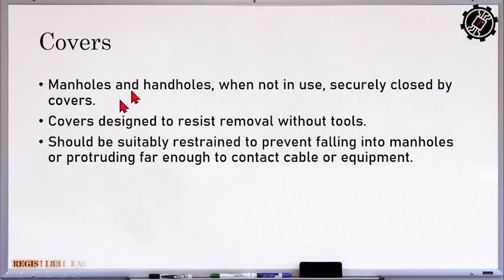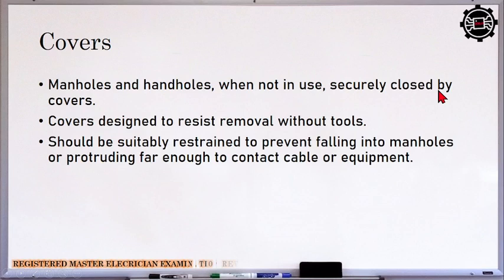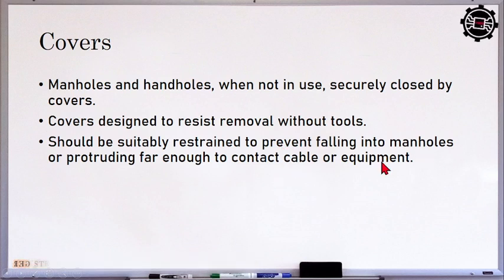So the cover, manholes and handholes when not in use must be securely closed by covers. So covers is designed to resist removal without tools. No, so dapat pwede lang ma-open yung mga cover ng ating manholes and handholes if there is specialized tools to be used, no? So basically, only the qualified person could access our manholes and handholes. Should be suitably restrained to prevent falling in the manholes or protruding far enough to contact cable or equipment. So dapat may siya tamang support so that walang mga taong mahuhulog sa manholes. Tapos it is also far enough doon sa cable natin na nasa ilalim.